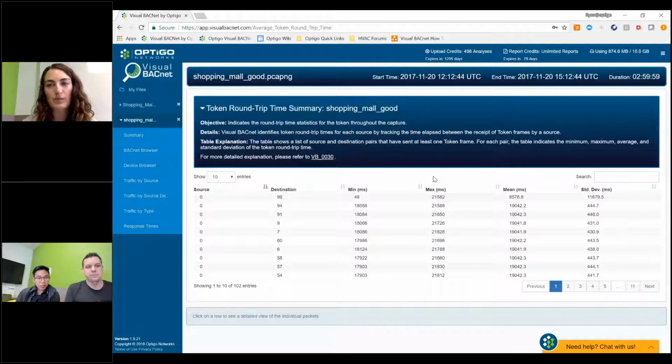Another Ryan just jumped in with a question saying, shouldn't these devices be sending to the next device and not back to 0? So yes, just to clarify, you shouldn't go back to 0 every time. It should go 1 to 2 to 3 to 4 to 5. That's the crux of what's wrong here. It's going back to 0 every time. And likely, if you solve that problem, a lot of the other stuff would get solved. But figuring out exactly why it's doing that would require looking at the physical devices. So this requires some on-site work.